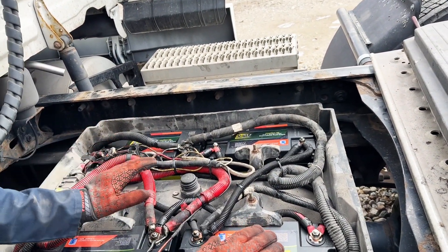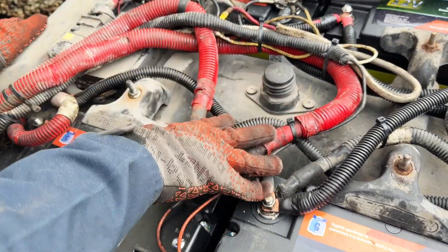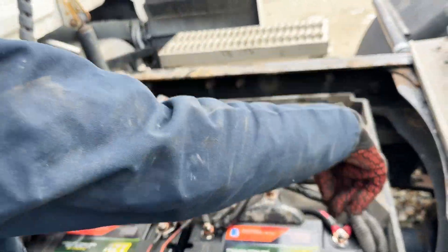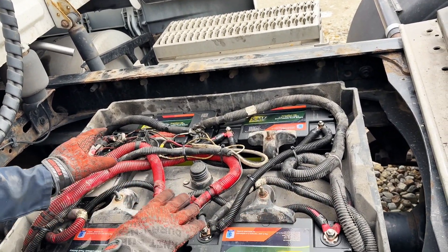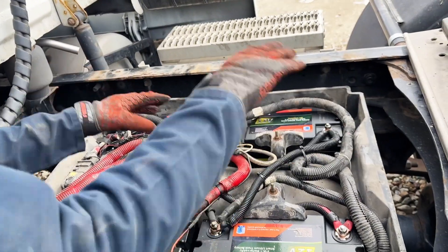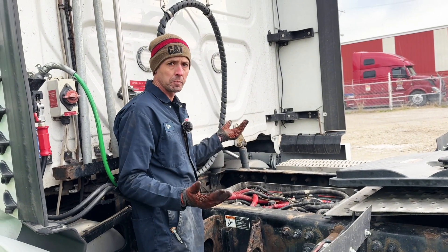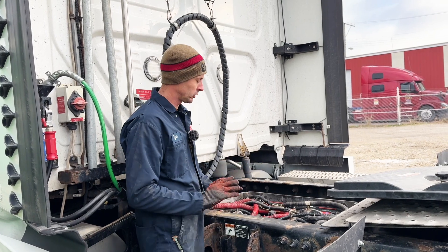One of the main things you want to make sure with your loads is that you want to charge on one end of the battery bank and discharge on the other end of the circuit, so that you're going through all four batteries. You're not favoring one battery. If you hook your positive and negative to the same battery, it's going to favor that battery — same thing with charging. You want your negatives and positives opposed so everything flows through all four batteries. That way your batteries stay healthy, all discharging and charging at the same rate, and you're not putting undue wear on any one specific battery.